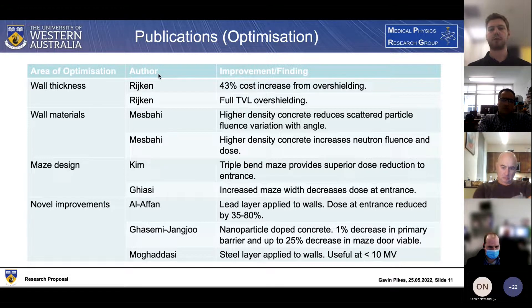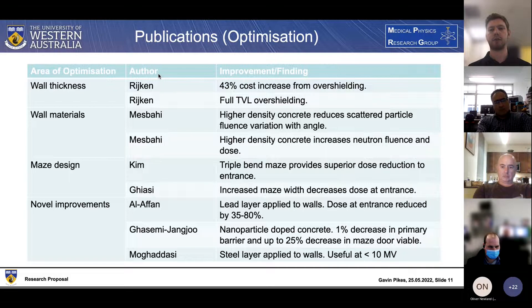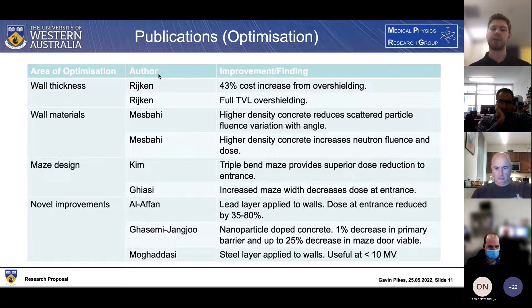High density concretes have been found to be quite useful in reducing the scattered particle fluence variation with angle. However, especially above 10 MV, you get problems with photoneutron production - these higher density concretes involve high-Z materials, resulting in higher dose to the patient from the wall material. In terms of maze design, one of the big findings has been that triple-bend mazes have shown to be superior at reducing the dose at the entrance of the maze.